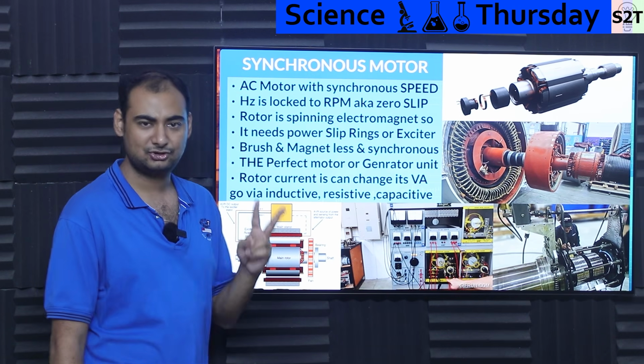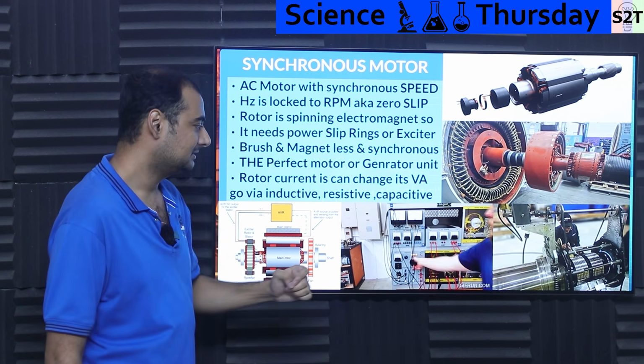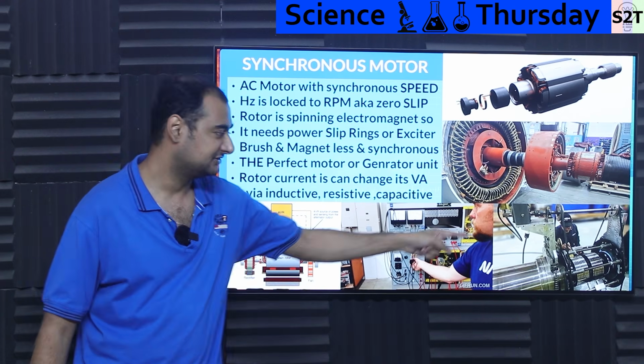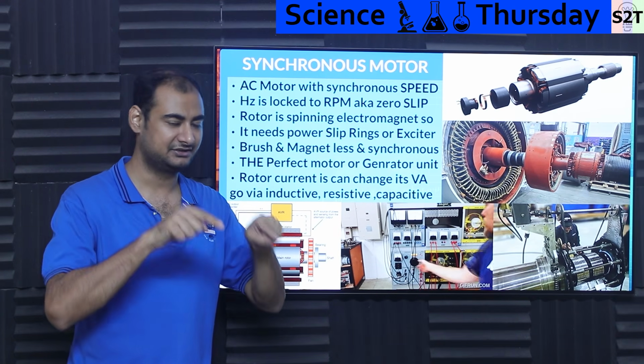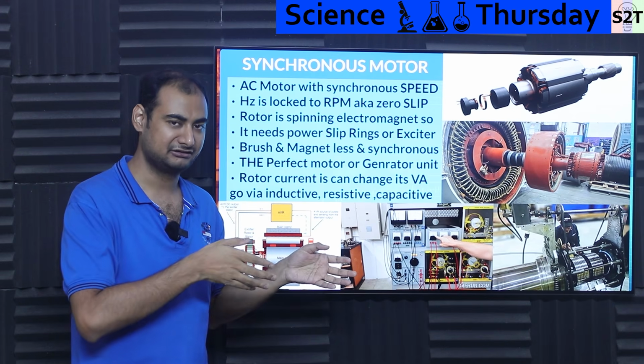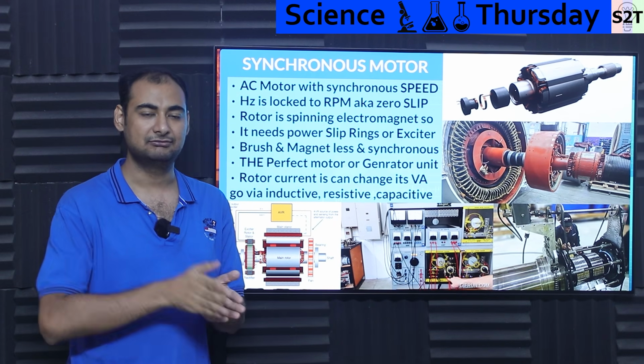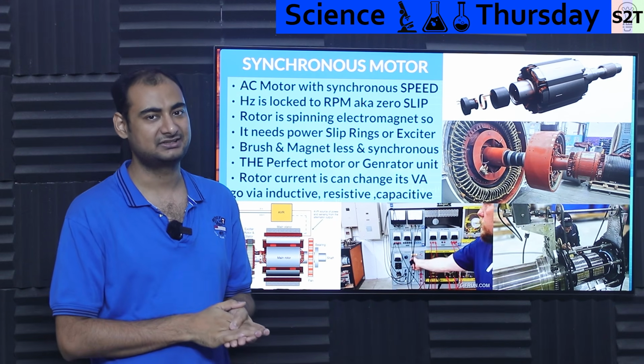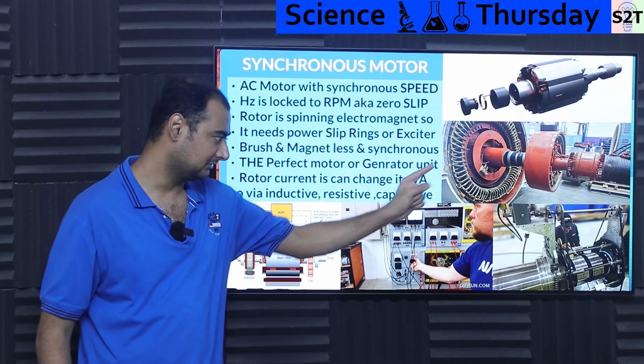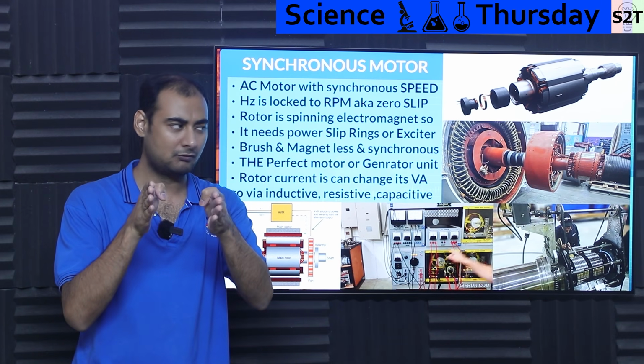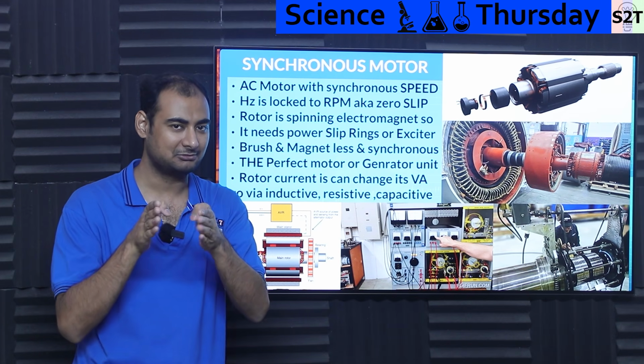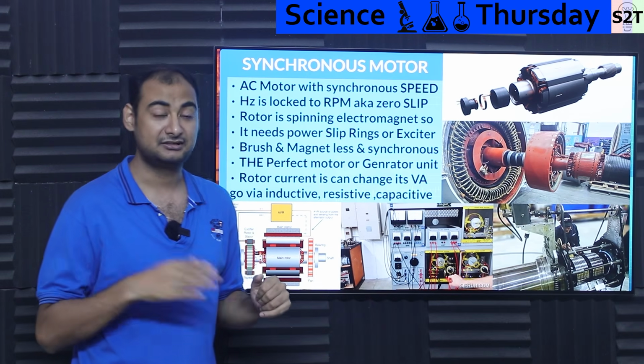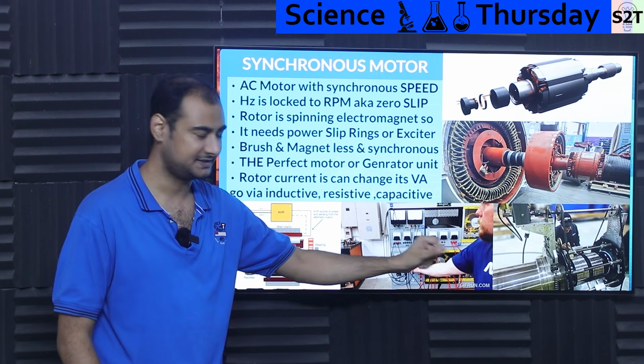So you utilize two options. One option is slip ring. You'll see giant power plants have slip rings. Slip rings is where you dump energy into the rotor, and that's the first line of control. Generally the steam valve handles it - if a lot of fluctuation is happening in the RPM, the steam valve responds, and all the frequency control happens on this level. Those fingers are like, whoa, too much power, too little power - that management happens hundreds of times a second on those puppies.